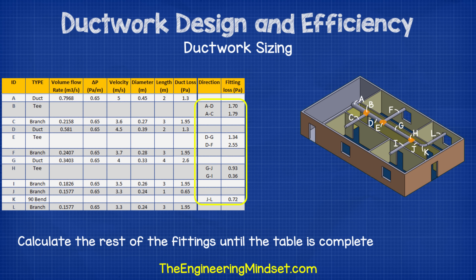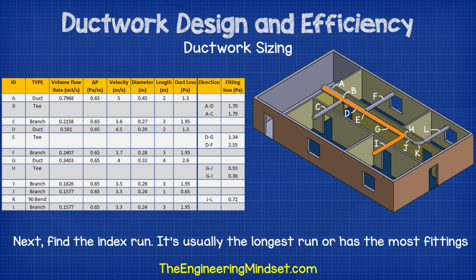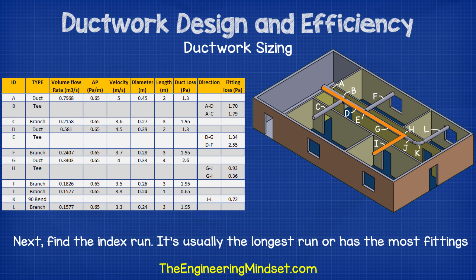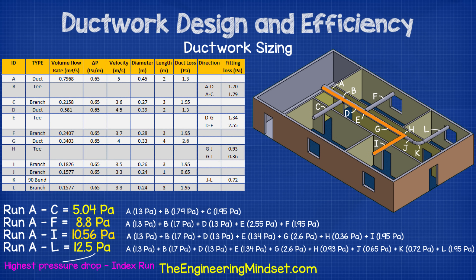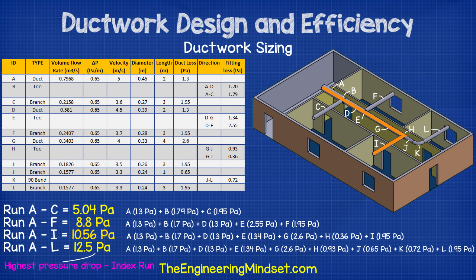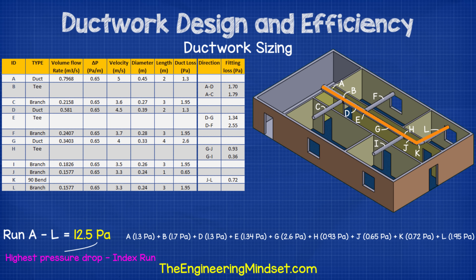Now repeat that calculation for the other T's and fittings until the table is complete. Next, we need to find the index run, which is the run with the largest pressure drop. It's usually the longest run, but it could also be the run with the most fittings. We find it easily by adding up all the pressure losses from start to the exit of each branch. For example, to get from A to C, we lose 5.04 pascals. For A to F, we lose 8.8 pascals. For A to I, we lose 10.56 pascals. And for A to L, we lose 12.5 pascals. Therefore, the fan we use must overcome the run with the highest loss — that being A to L, with 12.5 pascals — this being the index run.